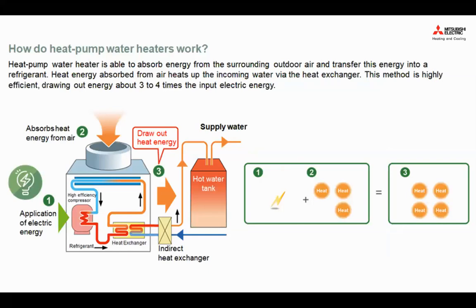So how does a hot water heat pump work? It is very similar to other heat pump technology, other Mitsubishi heat pump technology, or heat pump technology in general. You apply, let's say, a kilowatt of electric energy, and heat is absorbed from the surrounding air, and then that heat is used to heat the water. As I mentioned before, our QAHV has a COP of up to 4.11 based on a specific testing condition. So you can see that it's highly efficient. We're drawing 1 kilowatt of electric power, and combined with the heat absorbed from the air, we're able to achieve 4 kilowatts, a COP of 4.